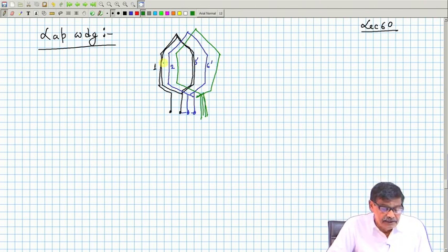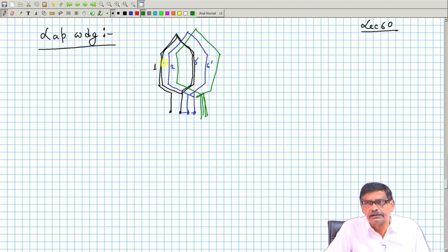If that be the case, that is fine as I told you, but we know that if a coil is moving, the stator field is stationary, nobody is rotating, because DC current you are passing to the coils and stator poles have become magnetized alternately as north south like that, and their magnitude is same and they are stationary in space. Unlike, say, an induction motor, it produces a rotating magnetic field. Therefore, to induce voltage in the rotor coils, to make it run as a generator, I must use a prime mover to run the generator.